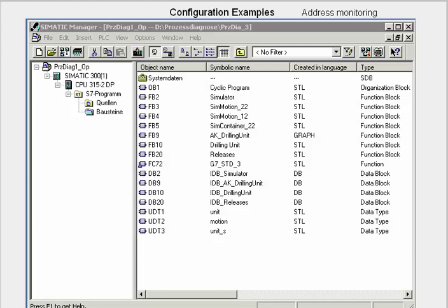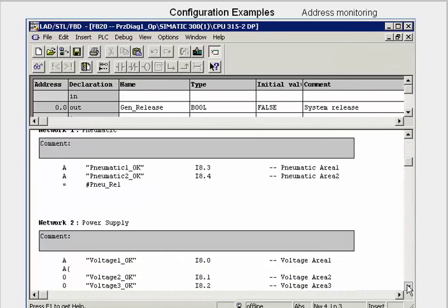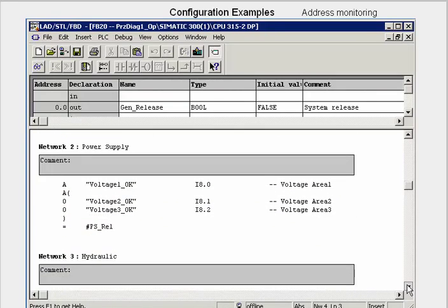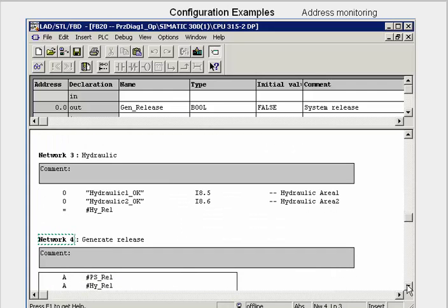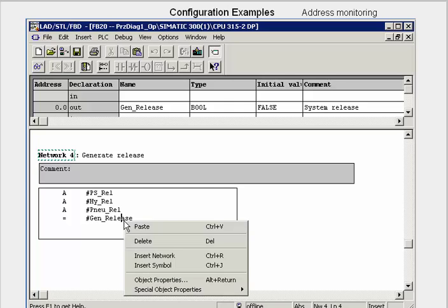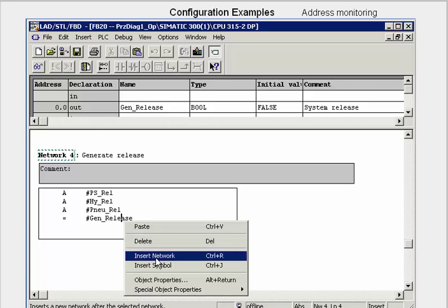Let us begin with the example of address monitoring with S7-P-Diag. We open FB20 in the block view of the Step 7 project. This contains a general run-release signal that is linked via an individual logic distributed over several networks. In Network 4, we select the assignment GenRelease and activate the Process Monitoring dialog.